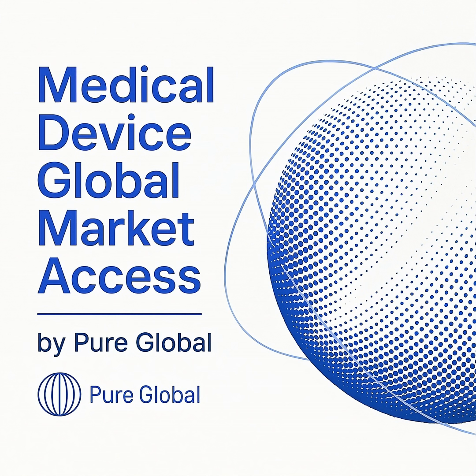This is where many manufacturers encounter issues. Appointing a distributor as the initial importer seems convenient. But if that distributor lacks a robust, proven quality system and staff trained in FDA compliance, your business is at risk. Shipments can be detained or refused at the border if entry filings and device listing information are incorrect. Worse, post-market compliance failures can lead to significant regulatory action. You must verify that your partner has the trained personnel and established processes to manage these critical compliance tasks effectively.